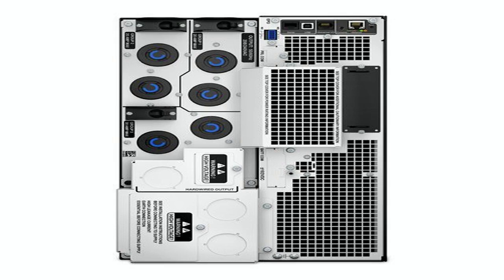Scalable runtime is a phrase you hear a lot, but what does it look like day to day? The unit comes with a base battery pack, but you can add additional battery modules in the same rack without shutting down your load. For a growing business, that flexibility is priceless. One of my clients started with a single 10 kVA load and added 2 extra battery strings after a year of expansion. They never had to pull the UPS out of the rack or schedule a weekend shutdown. The hot swap capability let the tech walk up, slide the old module out, slide a fresh one in, and the UPS recalibrated on the fly.